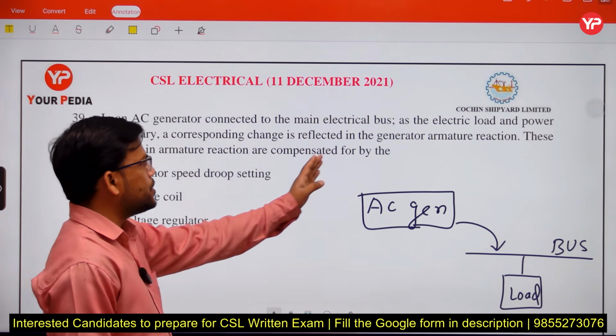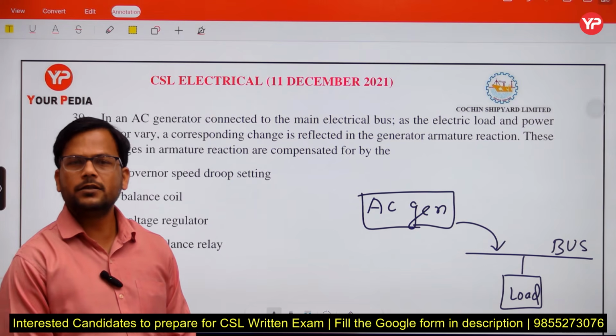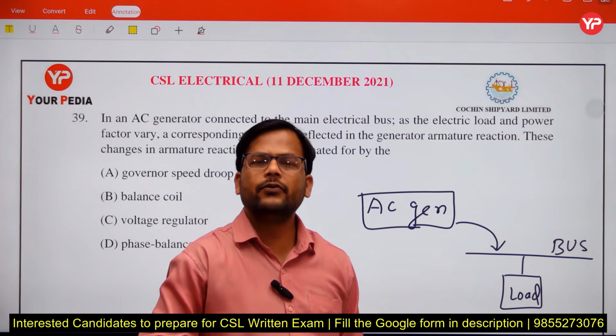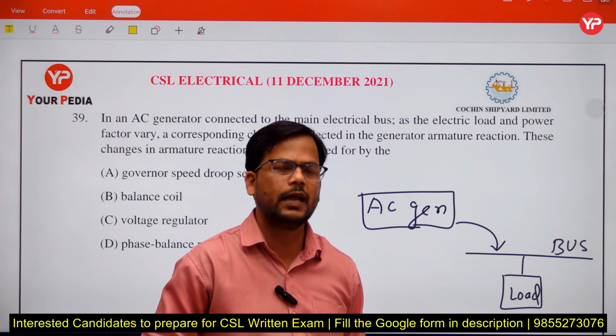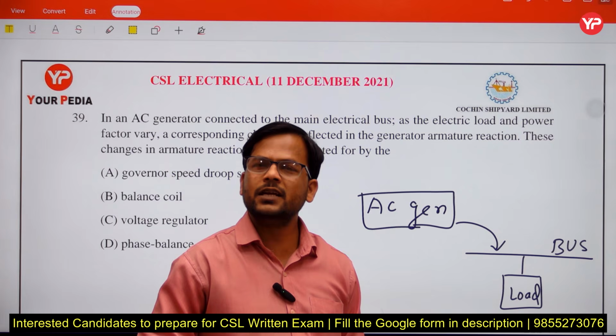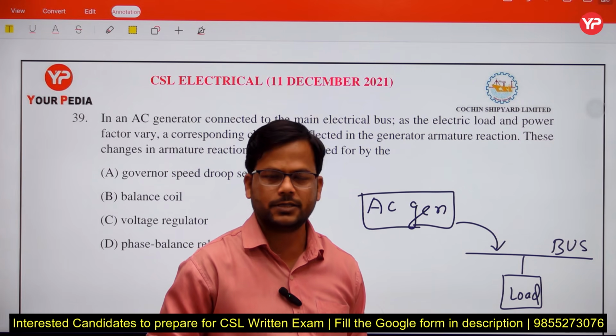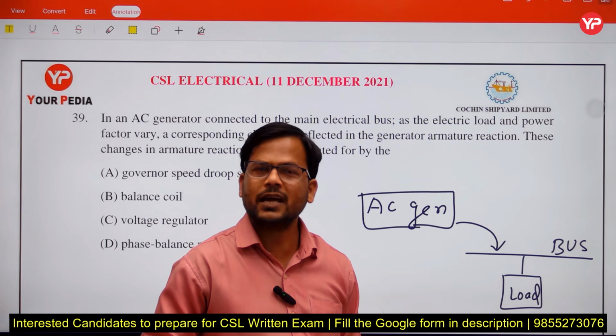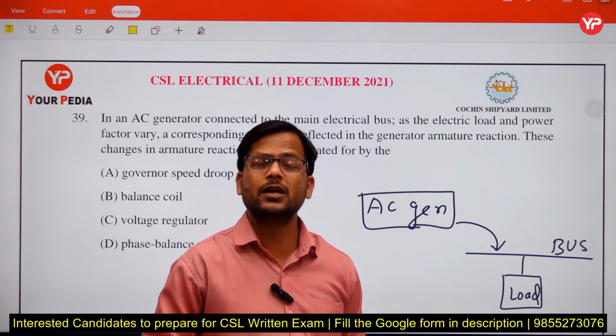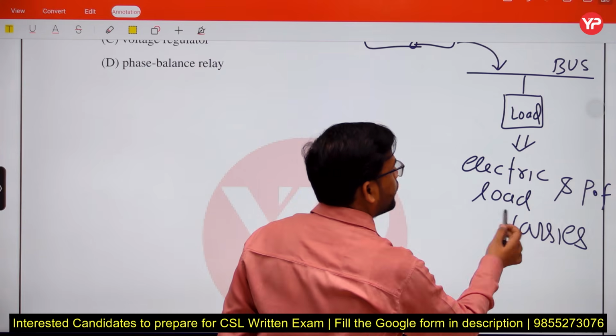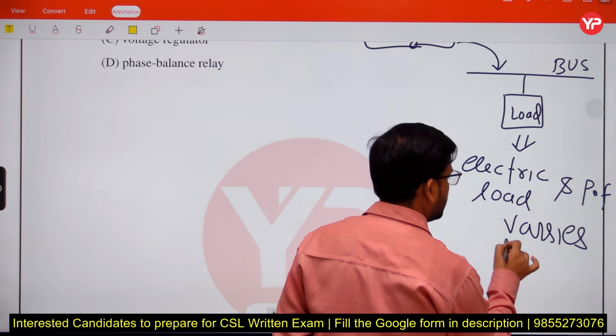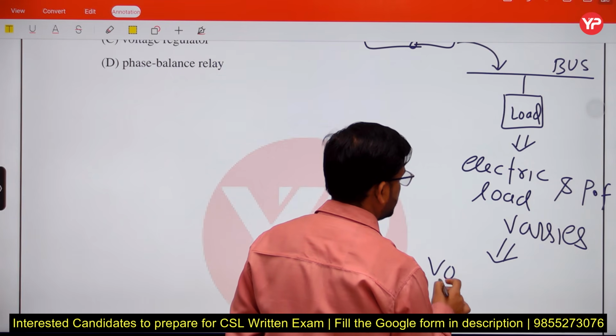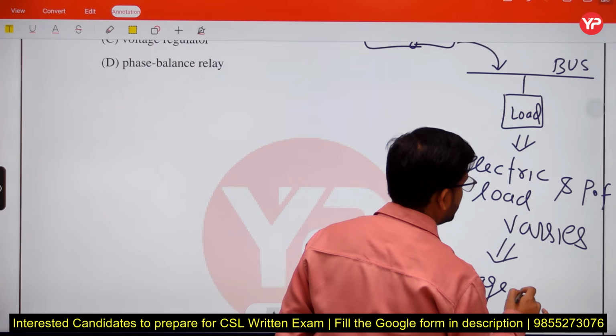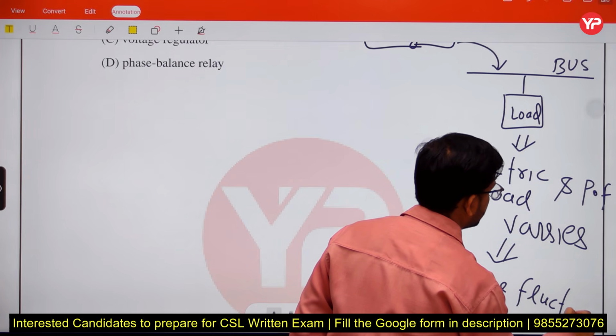A corresponding change is reflected in the generator armature reaction. We know in a synchronous machine, the effect of armature reaction depends on power factor, and if we change the power factor, the armature reaction effect arises. If the armature reaction effect arises, the terminal voltage starts fluctuating due to the varying electric load and power factor.